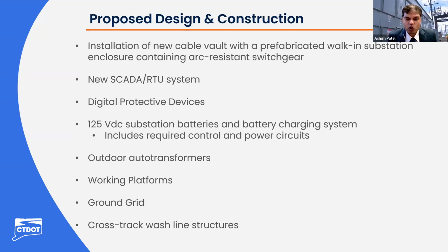The outdoor rated type autotransformer will be designed to balance the traction power voltage system. The cable vaults will be designed under the medium voltage enclosure. The working platform will be designed for maintenance of HVAC units mounted on the balancing substation enclosure. The ground grid will be designed to mitigate step and touch potential. The cross-track feeder will be designed to carry the disconnect switches and an aerial wire running on the New Haven main line.